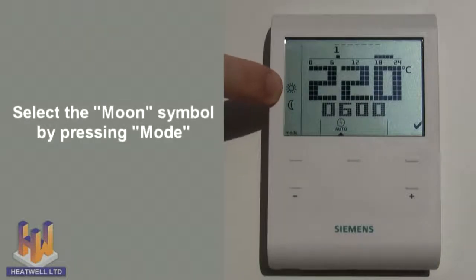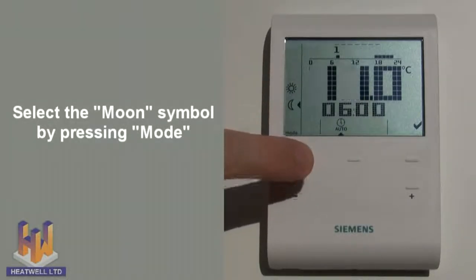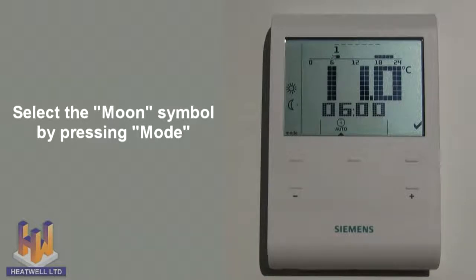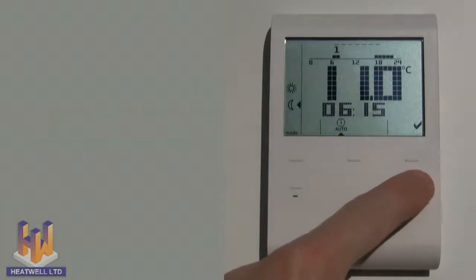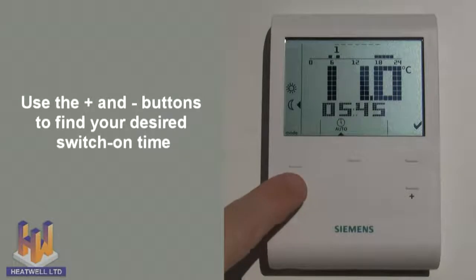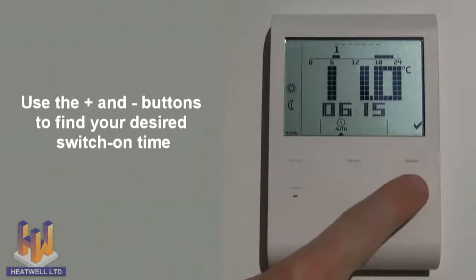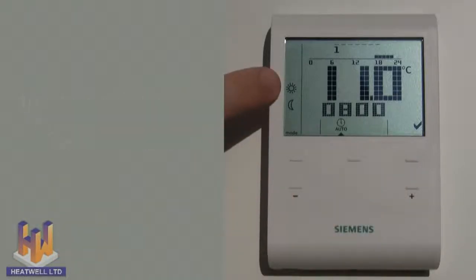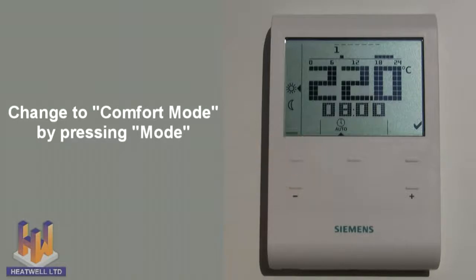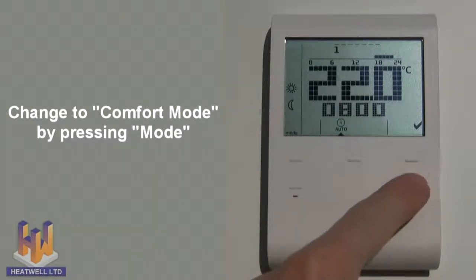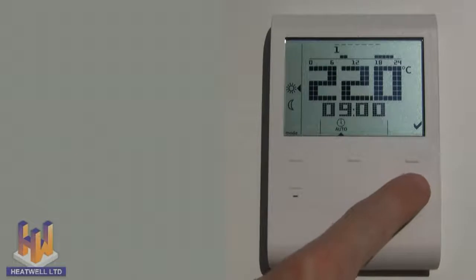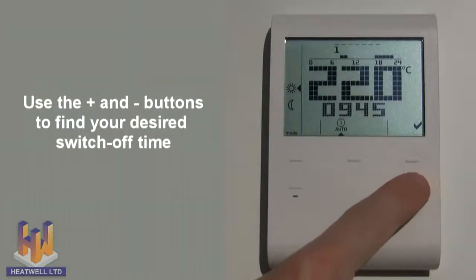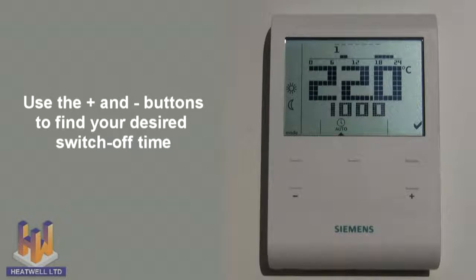In this case, let's set the floor element to switch on at a selected time in the morning. To do this, select economy mode or the moon symbol by pressing the mode button. Once in economy mode, press the plus or minus buttons to find your desired switch on time. In this case, I will choose 8 AM. When 8 AM has been reached, swap to comfort mode or the sun symbol. Do this by pressing the mode button. Then, continue pressing the plus button until you have reached your desired switch off time. In this case, the element will turn off at 10 AM.